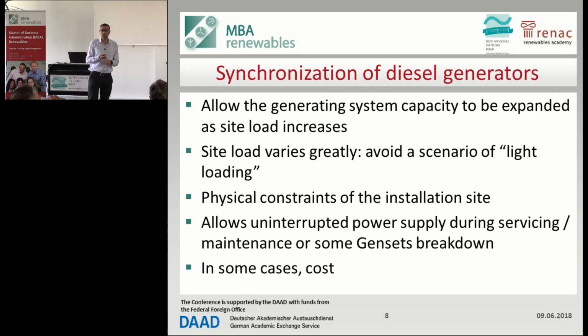Now the synchronization of diesel generators. It sounds like a big word, synchronization, but it's not more than operating more than one diesel generator on the same bus. All of them are working simultaneously to give the power for the load. It's very important and it's very helpful in many cases. For example, this ability allows you to extend the system later, to make it bigger, to add more diesel generators if required. It allows you to operate them smoothly.